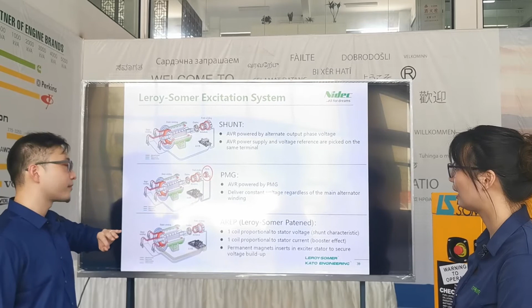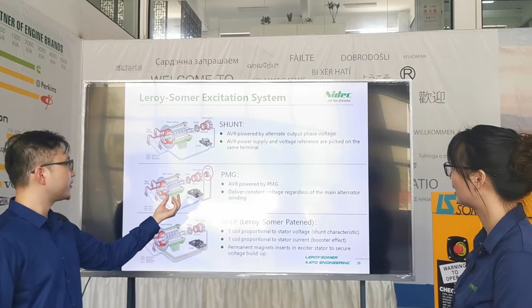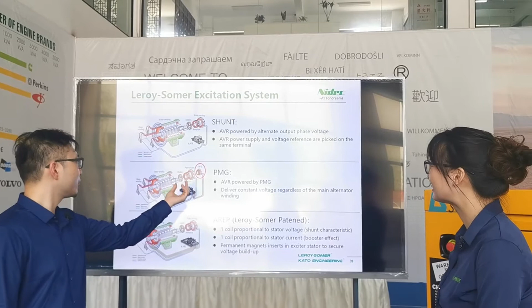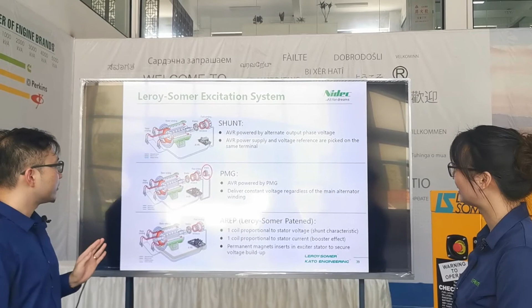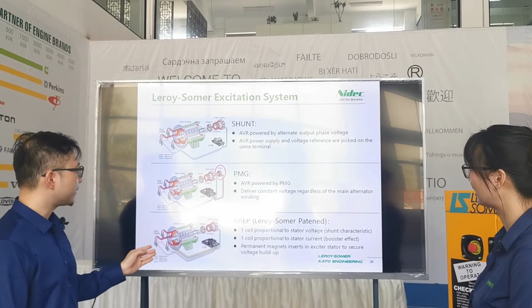And the difference between PMG and AREP - there are 3 differences. First, PMG is an additional component, an additional generator, which sits at the end of the machine, so the total size of the alternator is bigger, or the genset will be bigger. Even for bigger machines, the PMG will be bigger. So first of all, the size.